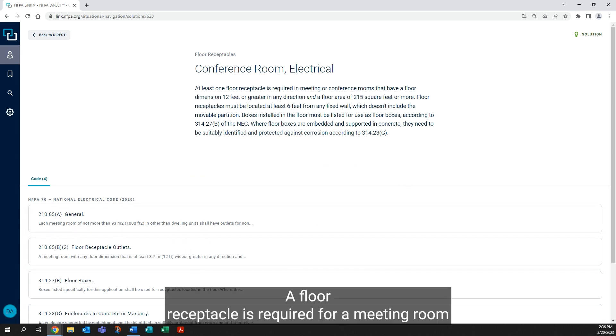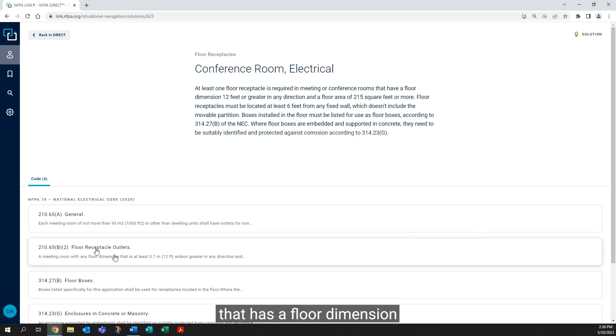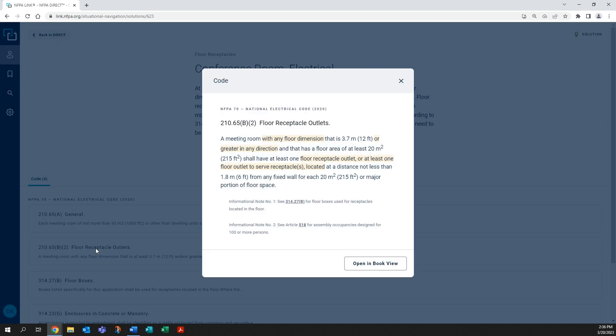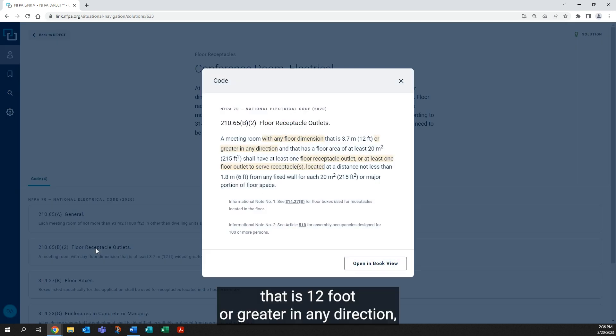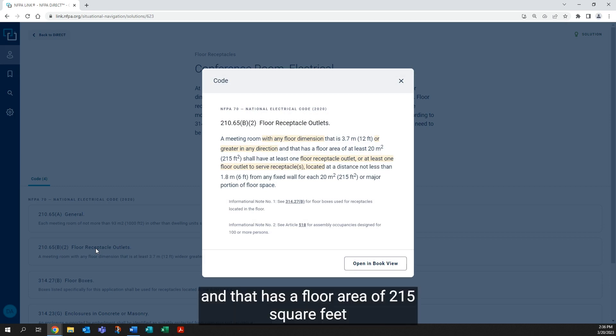A floor receptacle is required for a meeting room that has a floor dimension that is 12 feet or greater in any direction and that has a floor area of 215 square feet.